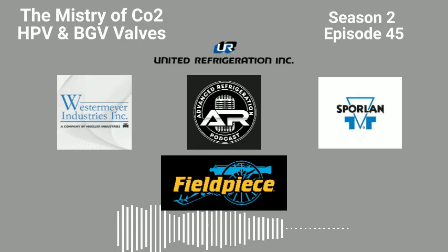So what I'm getting then is that when it's running transcritical, you're going to be using more energy, right? Because you're not making a really, really good liquid coming out of the HPV. So because you're having to flash off more liquid that's down at the bottom of the flash tank already to achieve a decent subcooling, there's more energy consumption there. Whereas if you were making straight up liquid when it was running non-transcritical, right, you're going to end up saving money when you're running subcritical, not just because of the compression ratio, but the quality of the liquid as well.